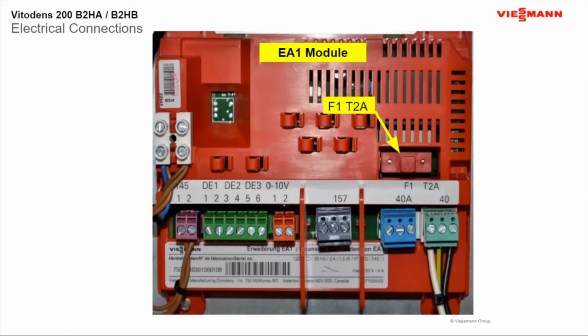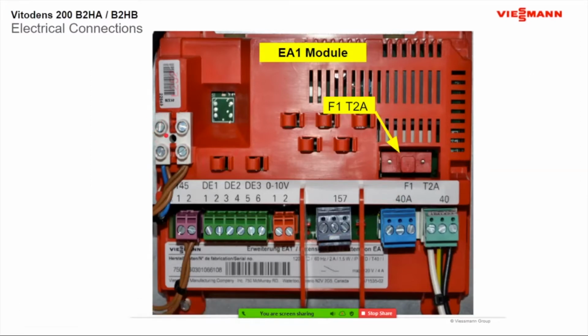Then the 145 communication here on the far left-hand side. This is where you would end if you were using our three-way mixing valve for a radiant or anything like that. You would just send the 145 communication over to the boiler. It now knows that you have our mixing valve connected to the boiler. So remember, auto recognize on most of our sensors as well. Our mixing valve comes with its own outlet temperature sensor that goes into a box that you plug into the wall, and your circulator goes into that as well.